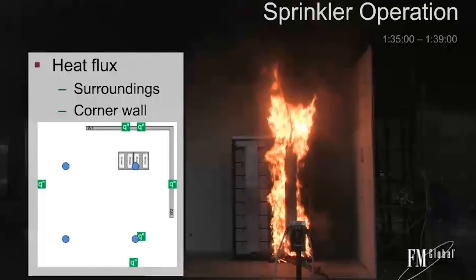The other reason is that as fires get larger and the radiation from the fire increases, the walls present a boundary condition where they can re-radiate and push that heat back to the energy storage system. That's another form of heating that can help speed up the fire development. I want to make sure that I am catching that effect. Now in this picture, all these green squares with the Q double prime are locations of heat flux measurements.